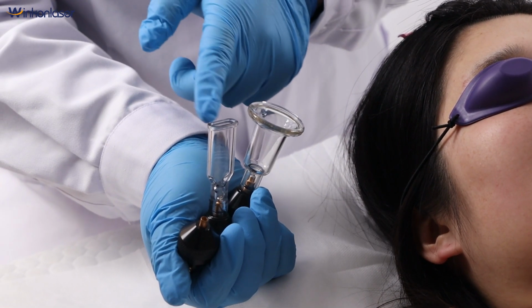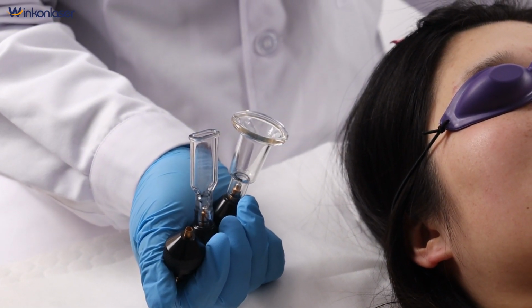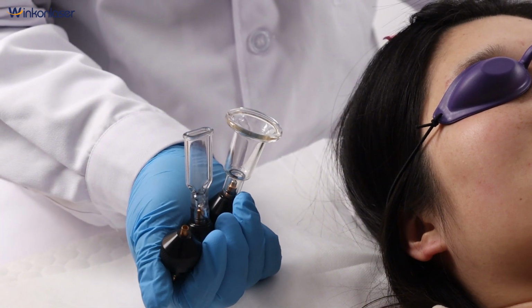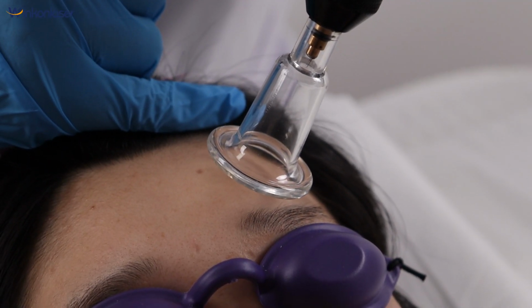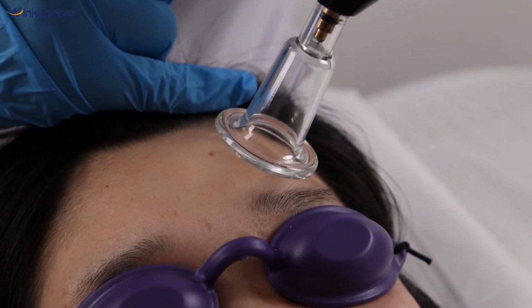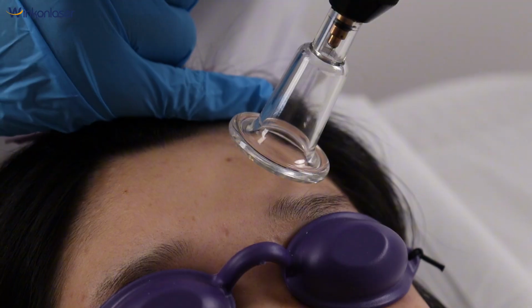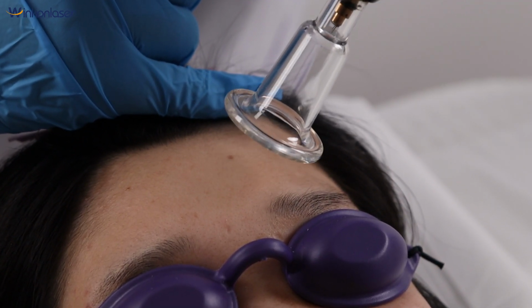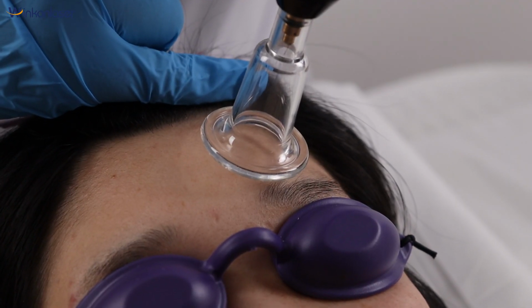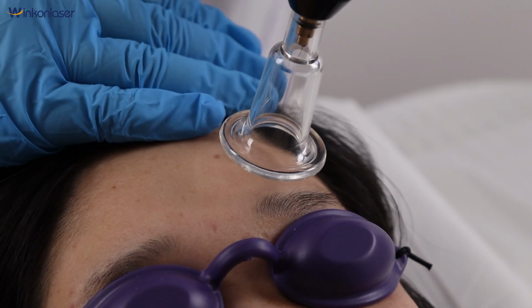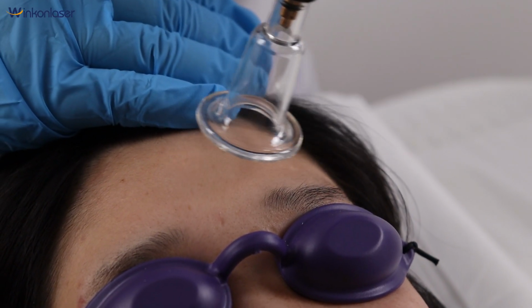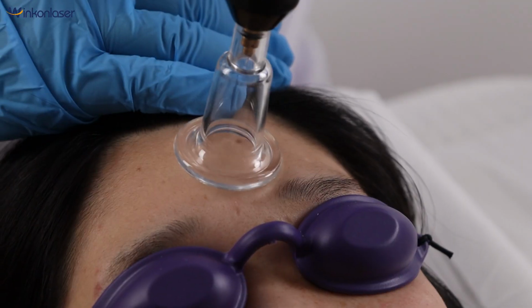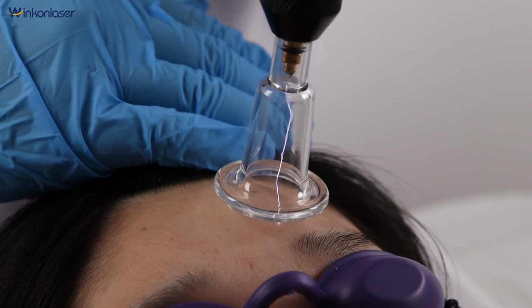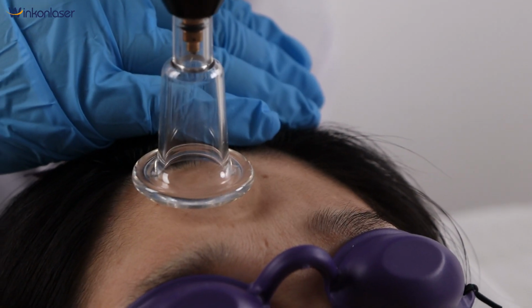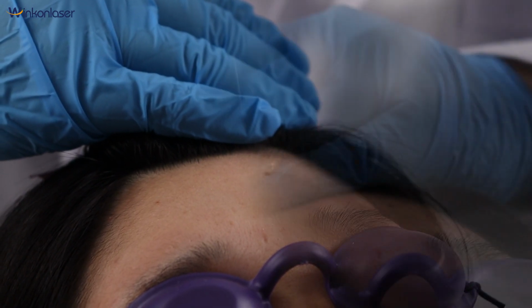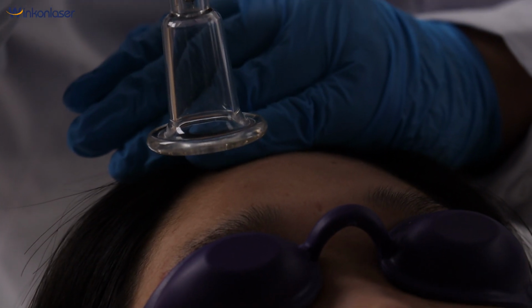First step, start with these 3 probes. Choose the probe based on the treatment area. Start with energy 4, and if your patient tells you of any discomfort, you may lower the level. But as long as they can accept a higher setting, you can make the energy stronger. The distance should be about half a centimeter. Start with a test shot. Do not stay in the same spot. Make sure the handpiece is moving. Keep sliding until the skin shows redness.